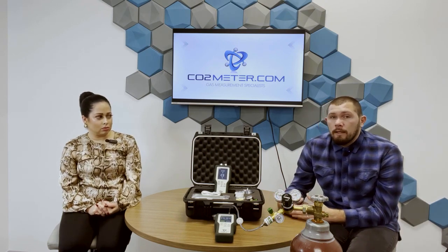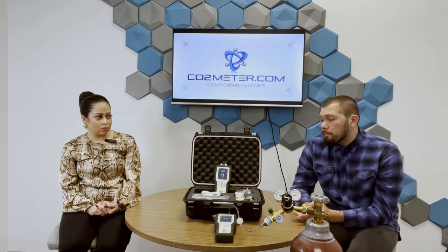If for some reason you'd like to do that calibration in the field, that's not an issue at all. As we showed earlier in the menu, you can access those calibration features, so it's not a problem if the customer wants to calibrate and do that maintenance in the field. We just suggest following that calibration procedure to a T, and making sure you're getting accurate calibration gas from your local suppliers. If you have any questions, contact CO2Meter and a technician will gladly walk you through that process.